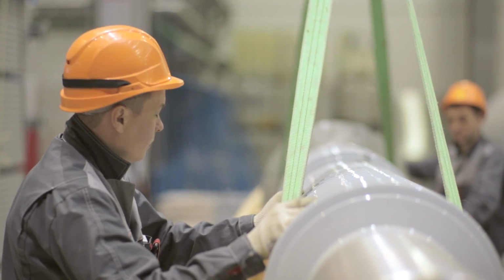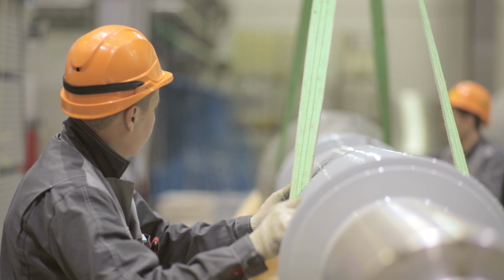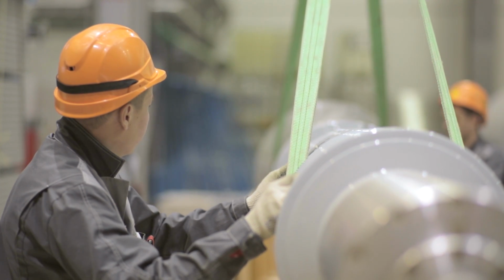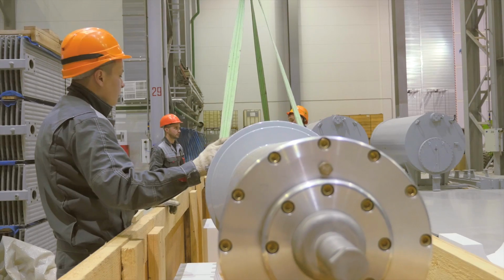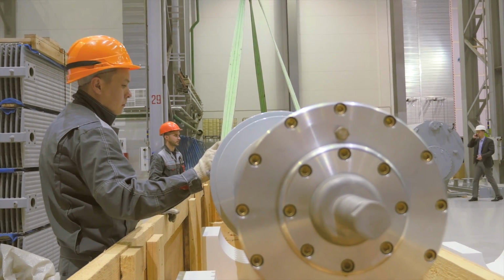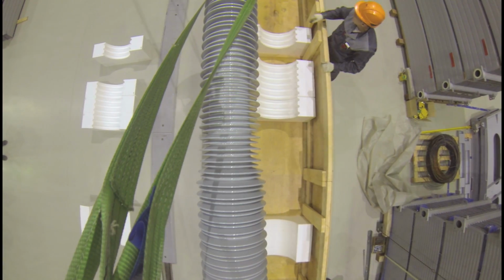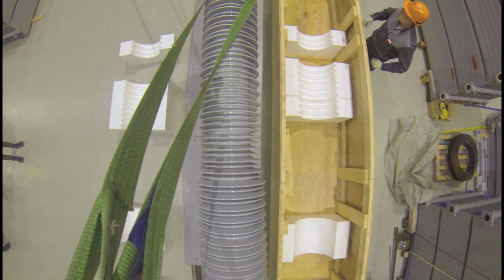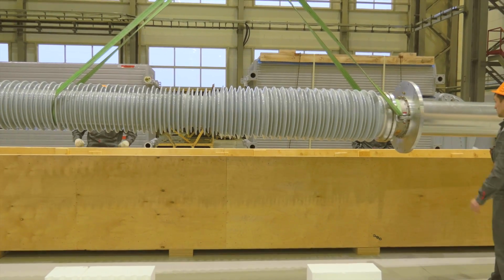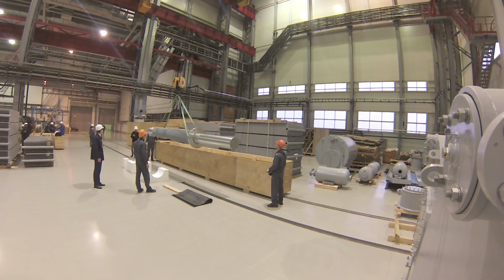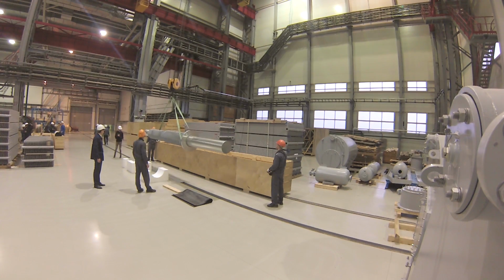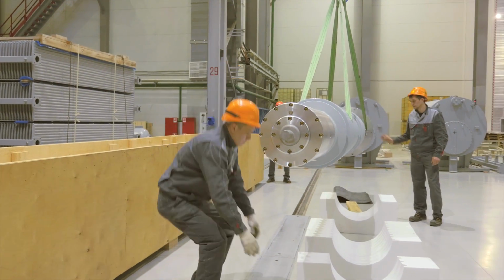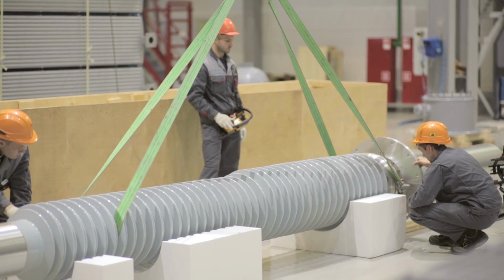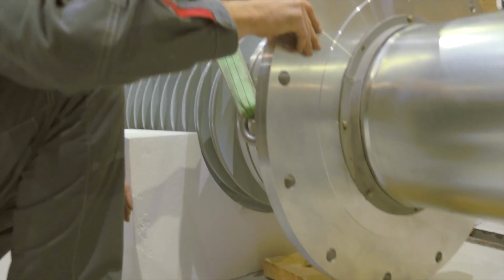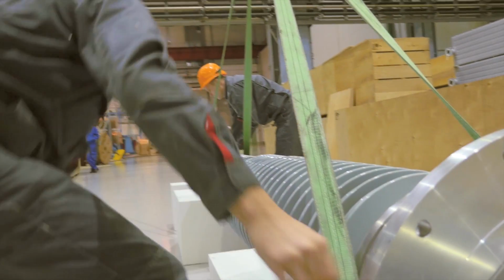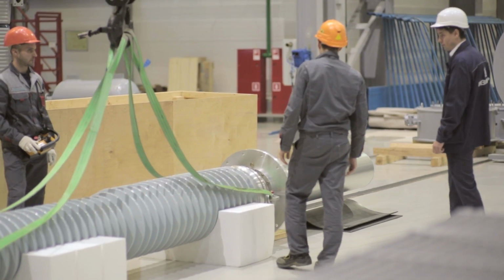Smoothly lift the bushing above the package to minimum height and make sure it is level. If slanted, put it back in and tie it up using other sheds. Only after it's done, you can remove the bushing and perform further operations. Put down the bushing with the porcelain housing resting on the polystyrene pads that you prepared.